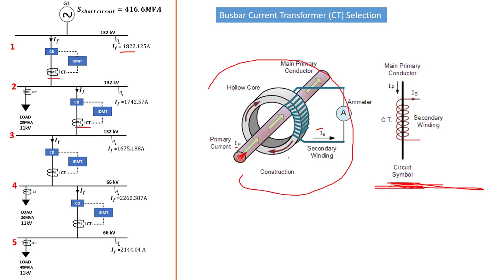According to the process of transforming the current, this is the same process as normal transformers work — a voltage transformer — that works on the phenomenon of electromagnetic induction. According to Ampere's law, together with Maxwell's equations, it says that if a magnetic field is integrated around a closed loop of wire, the value of that integral is equal to the net current enclosed by the loop of the current transformer. This basically means the current produced based on the magnetic field generated by the primary current will be a representation of the current passing through here.